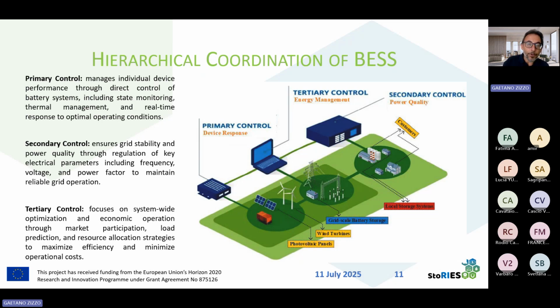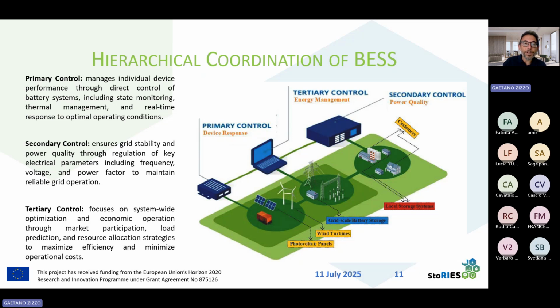The secondary control ensures the grid stability and the power quality through regulation of key electrical parameters, including frequency, voltage, and power factor to maintain reliable grid operation. So the secondary control is the one, for example, that coordinates all the battery units in the system for frequency regulation, for voltage regulation, and avoiding grid congestion, and so on.